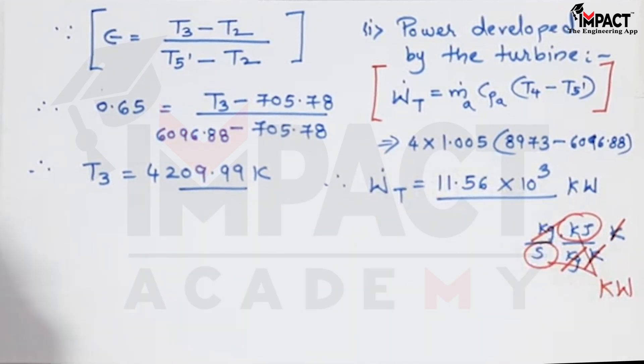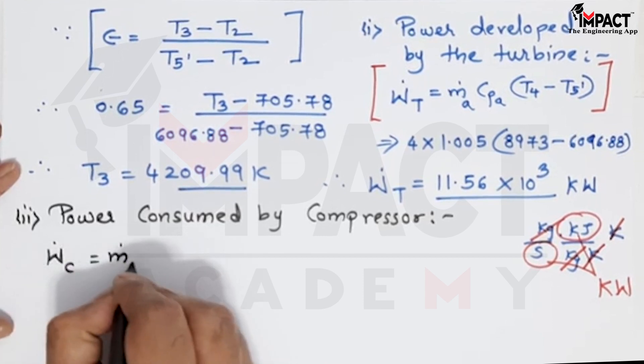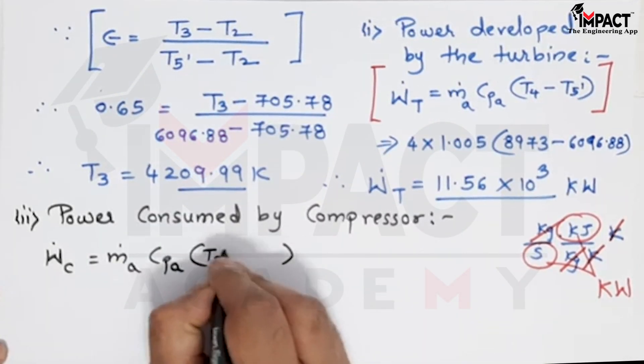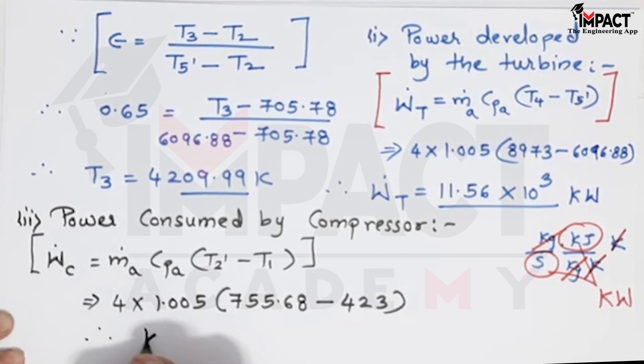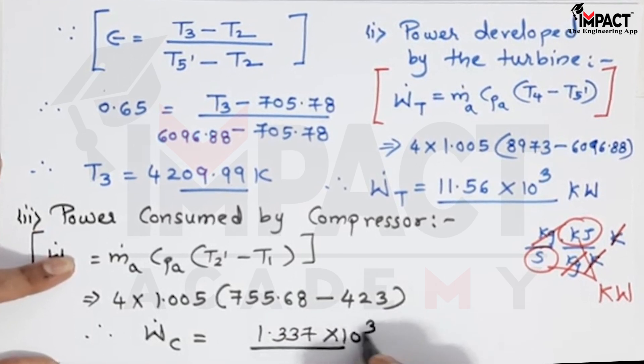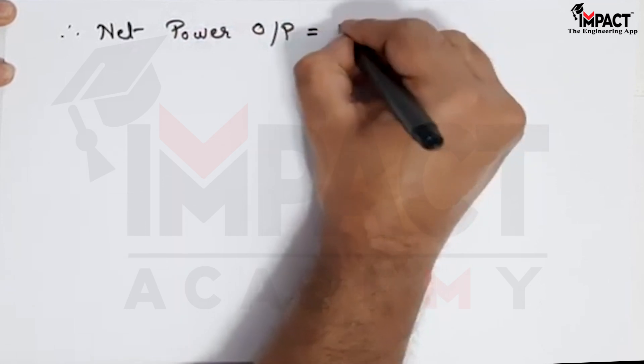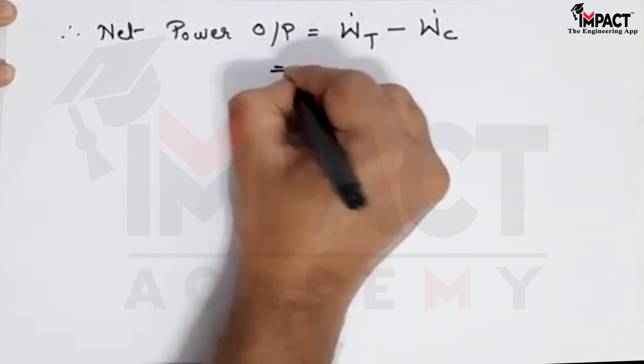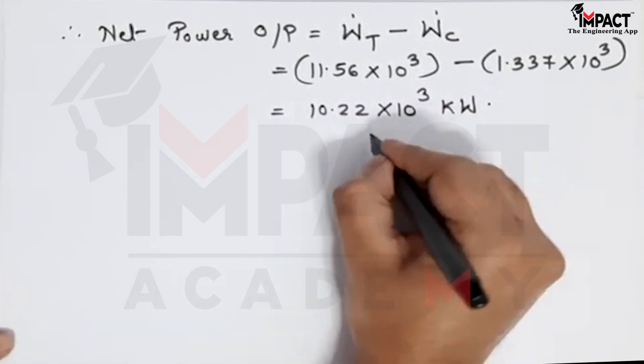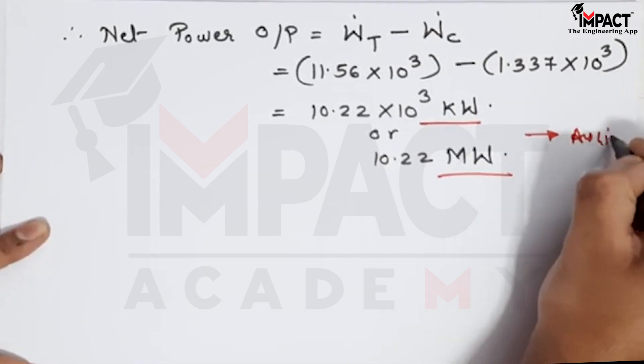Power consumed by the compressor is mass flow rate × specific heat of air × (T2 dash minus T1). Calculating this gives compressor power as 1.337 × 10³ kilowatts. Therefore, net power output equals turbine power minus compressor power, which comes out to 10.22 × 10³ kilowatts, or 10.22 megawatts.